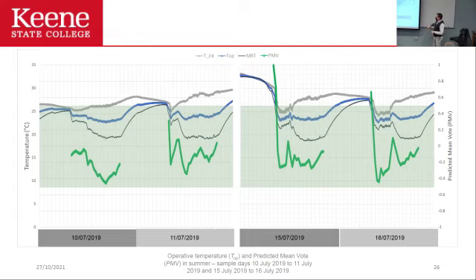So we ran the simulation and we are within this rectangle. When the system is operating, you can see the results, but when the system is not operating, at the beginning it's too hot. Everything above 0.5 is hot, everything below negative 0.5 is cold. We are in summer, so if you don't do anything, the predicted mean vote shows it's going to be too hot.